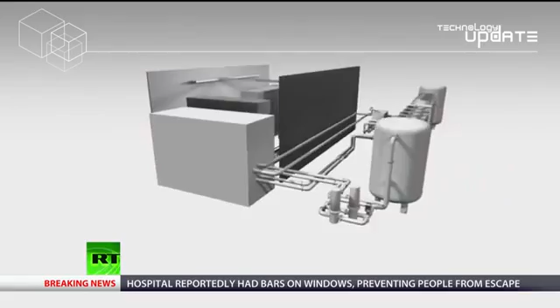The resulting setup is both environmentally friendly and allows for denser arrangements. The liquid cooling system enables us to place blade servers very close together in the server rack, raising the computer performance to around 180 teraflops per rack. This is a record achievement of ours that no one has been able to emulate so far. Additionally, by using liquid cooling technology, we're able to effectively remove up to 100 kilowatts of heat from each rack.